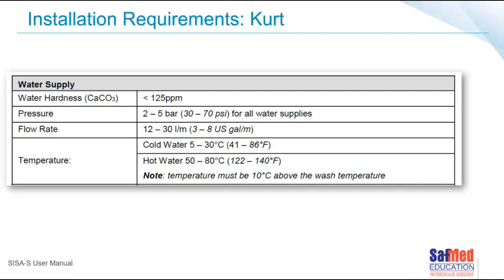If the water is too warm as well, there are machines that will create errors, or it will affect the cleaning efficacy of the ultrasonic cleaner. The water temperature could even end up aborting a cycle. 100%, it will abort the cycle. A lot of the fully automated units I've seen from the brands on the market definitely abort the cycle if it's too cold or too hot. So the water temperature has to be within the manufacturer's stated values. That's actually a good safety feature. If the water is too cold, you're not going to get good cleaning, or if too hot, you might almost bake on the proteins. So it's a nice safety feature to make sure the water temperature is correct.